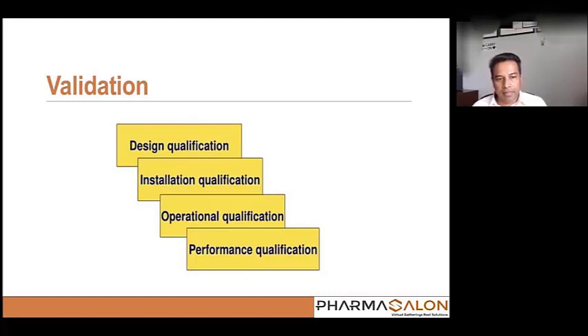And what is the intention of using the particular autoclave or dry heat oven, such as depyrogenation or sterilization, things of that nature? And what capacity do you need? What is your maximum batch size? How often will you be using this? So all these parameters need to be considered prior to selection of the equipment. That is basically design qualification.